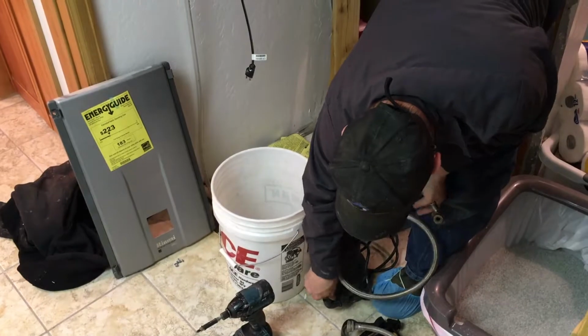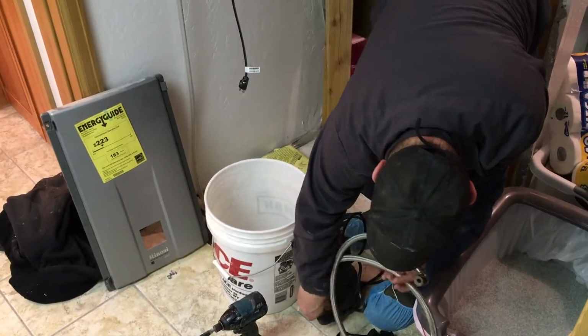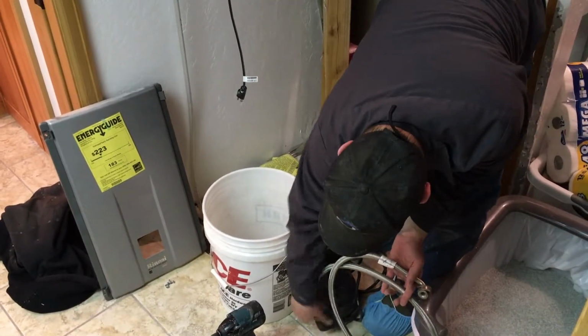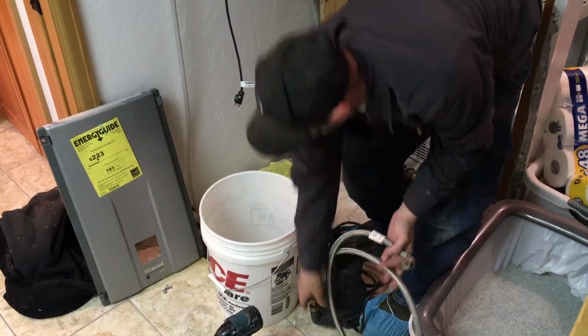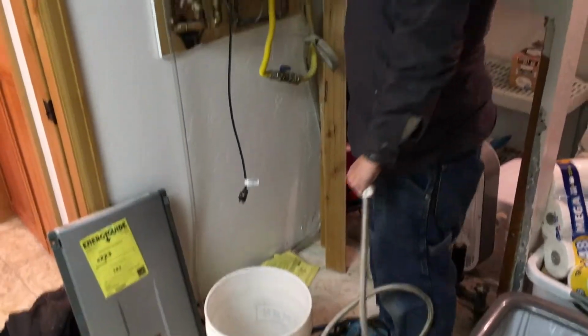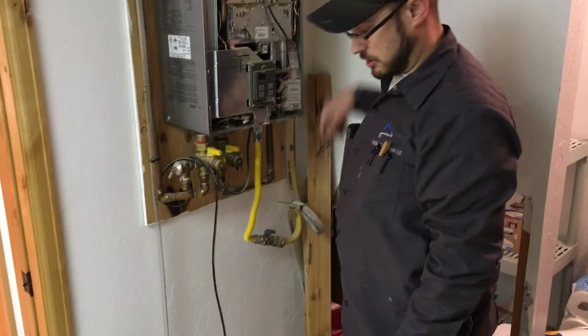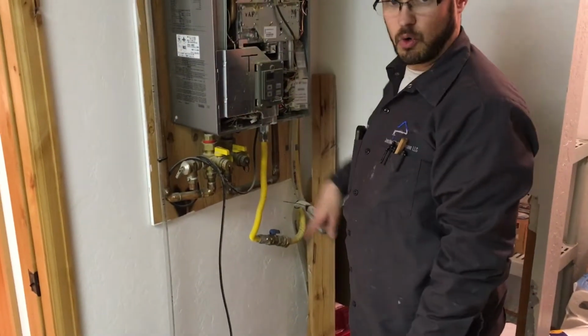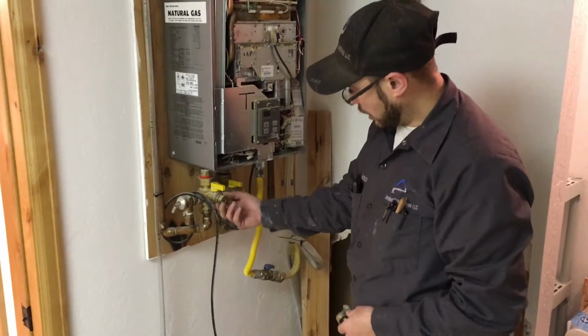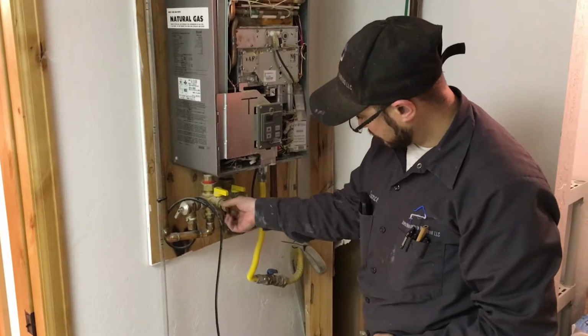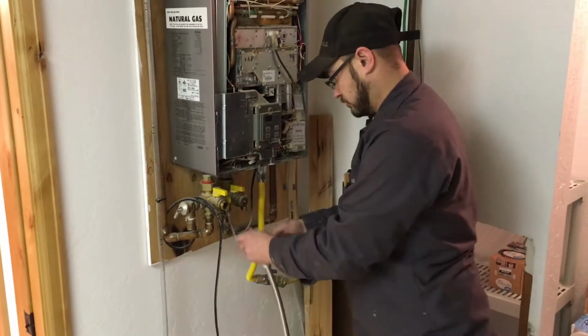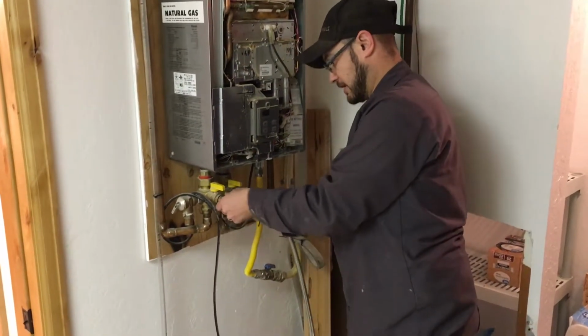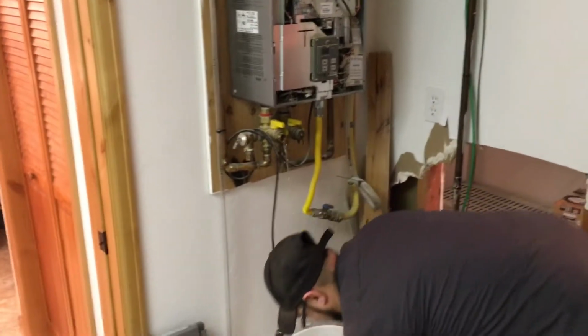What you want to do is hook this pump up to the hot side, because we want to pull the water and all the chemical we're going to use to clean through the coil. So we'll hook it up to the hot side, which is always going to be on your left hand side here. I'm going to do this real quick, try to get it in there without it leaking water everywhere. It's not doing too good.